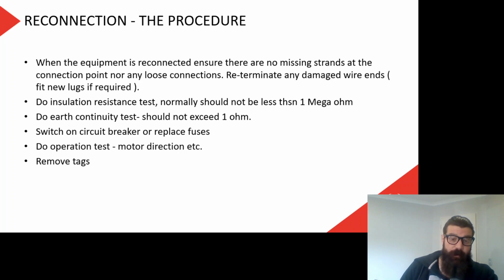We should do an earth continuity test on the equipment that we've reconnected, or the new equipment that we're installing. So that means that the earth wire from the wall is continuous to the body of my appliance, and it should be less than 1 ohm. Well, it must be less than 1 ohm, not should, must.